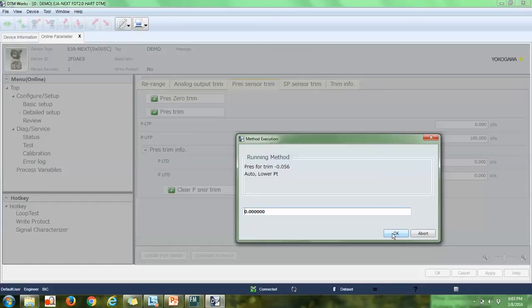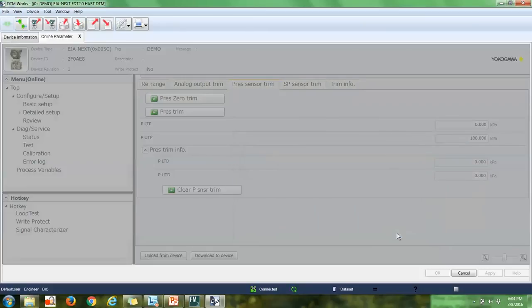And again, our pressure transmitter is reading negative 0.056, so that's what the actual transmitter is reading. And then, if you're hooked to a calibrator, you would put what the calibrator is reading in this field to make your adjustment. In this case, my transmitter is open to atmosphere, so I will go ahead and make this trim.